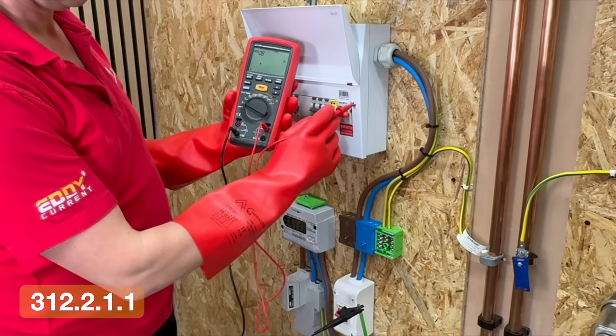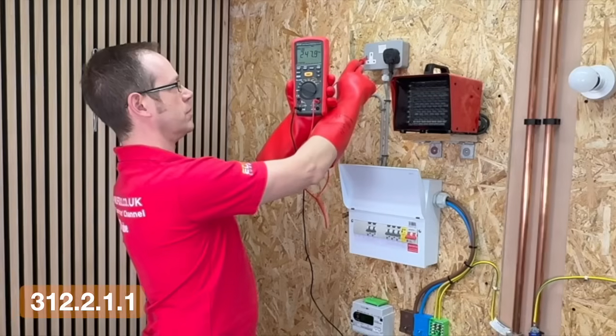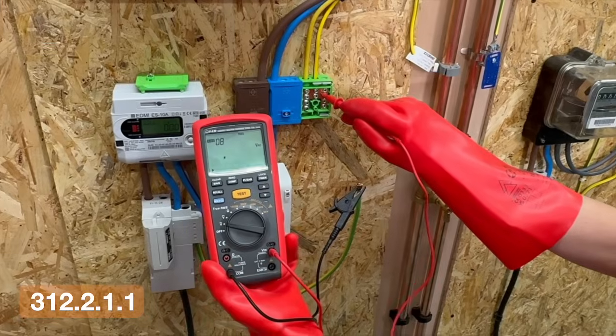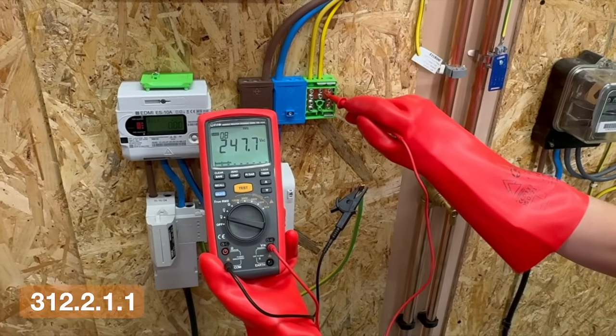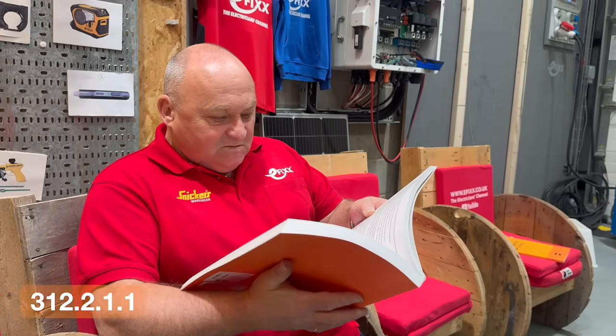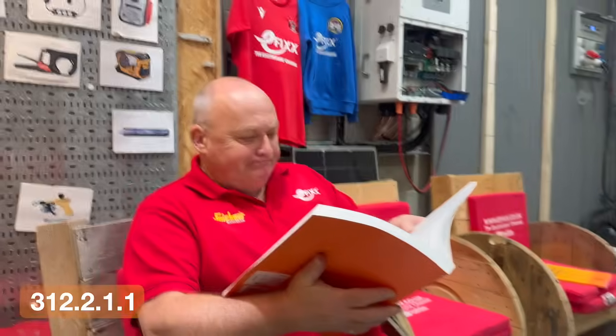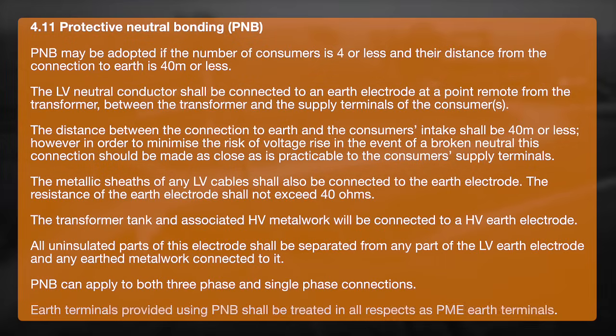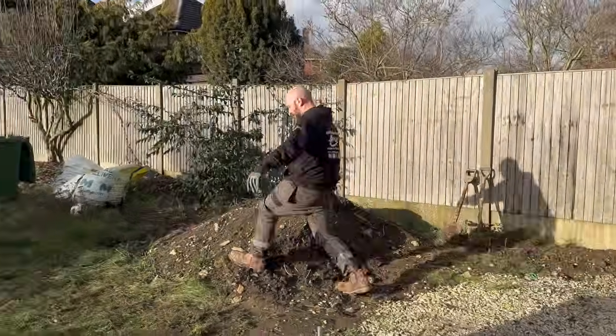The reason for this is to reduce the risk of voltage rise if the PEN conductor becomes open circuit. If that happens, the installation can rise towards line voltage. Adding an earth connection closer to the building helps limit that rise. BS 7671 now recognises this arrangement, but it does not define how it is implemented in detail. That is covered by external guidance such as the ENA Engineering Recommendation G12. In real installations, this earth connection is typically made relatively close to the point of supply, often within tens of meters of the intake, although that distance comes from guidance, not directly from BS 7671.